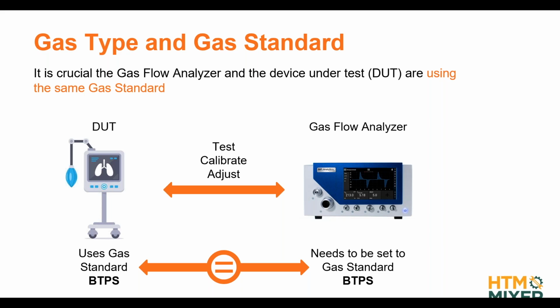No, unfortunately not. That's why you will see on ventilators, usually you have a whole selection of different gas standards. The most common ones are BTPS and STP. That's different standardization on different temperature, pressure and humidity. The only thing is, you really need to figure out what your device under test uses. In most cases, it's going to be BTPS, but again, it can be different. Usually, they specify that somewhere in service manuals or user manuals. If not, if you ask them, they should be able to give you that information.